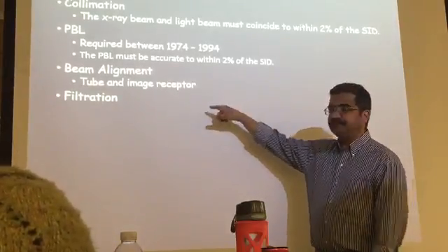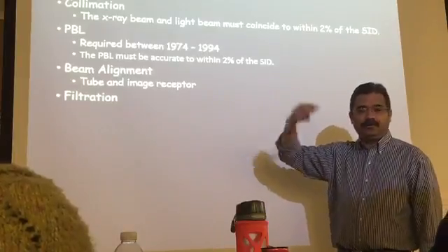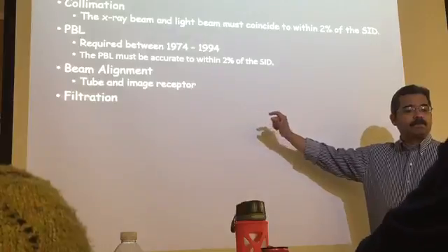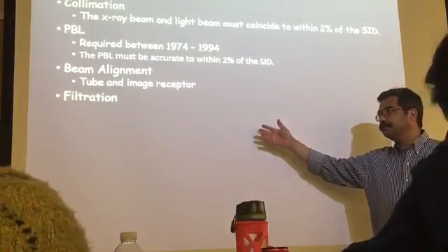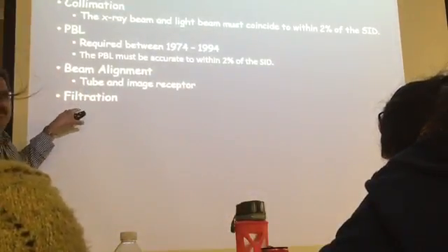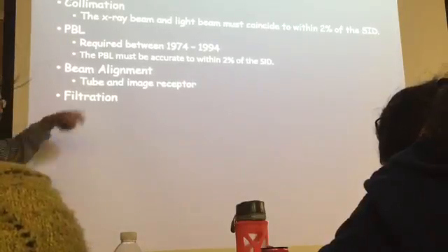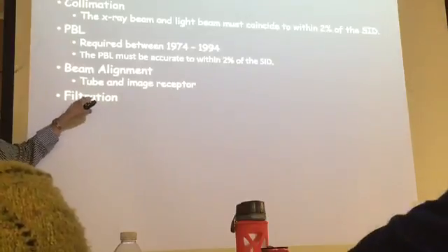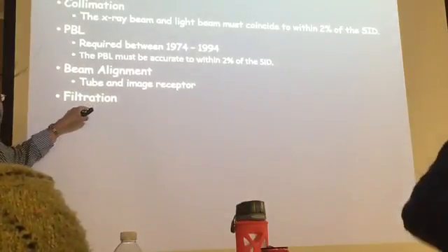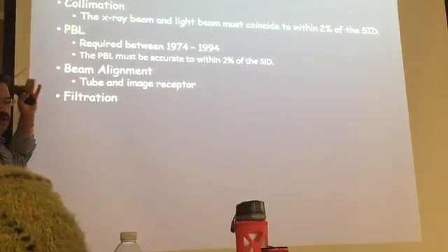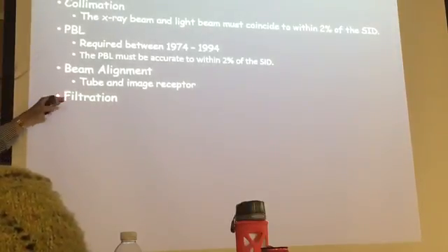When you do that test, which is another test that physicists will do once a year, you measure that. And what you find is that manufacturers, I've never seen one that even comes close, are always going to have more than 2.5. 2.9, 3, 3.2 is common to see.